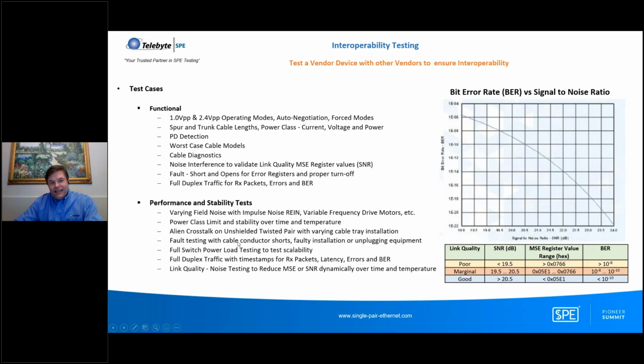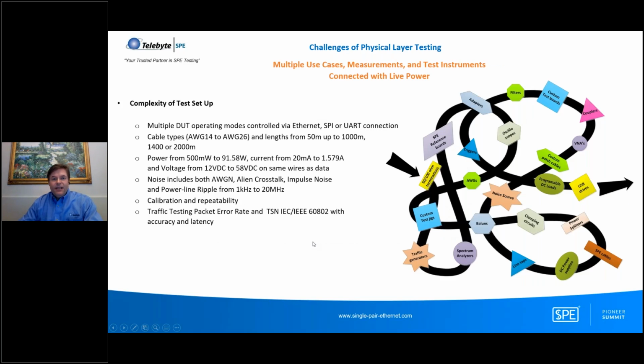And we're doing fault testing where we're unplugging equipment or shorting some of the wires to shield, or shorting the differential pair, just to test what may happen in the field. So those are the definitions of tests. There's quite a thorough amount of tests to make sure that the equipment is working correctly and it's in the standards.